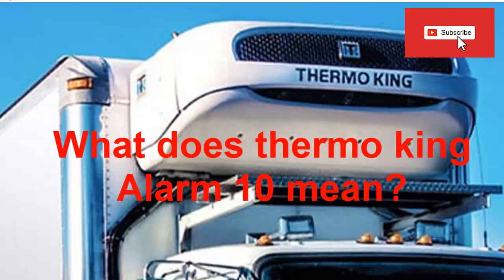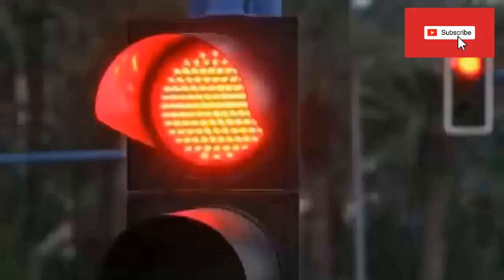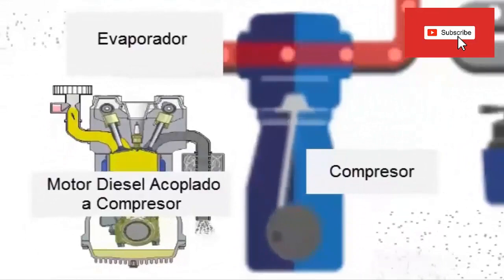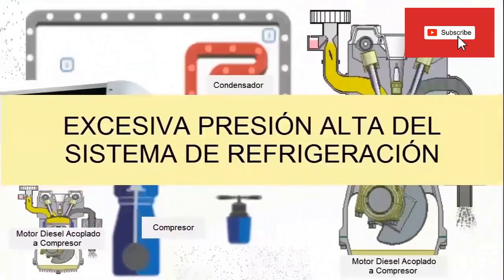What does Thermo King Alarm 10 mean? This alarm is identified by the manufacturer as red, which indicates that if its activation is repeated, action must be taken immediately, since it effectively corresponds to a serious problem. Thermo King Code 10 is related to high compressor discharge pressure from the refrigeration cycle.